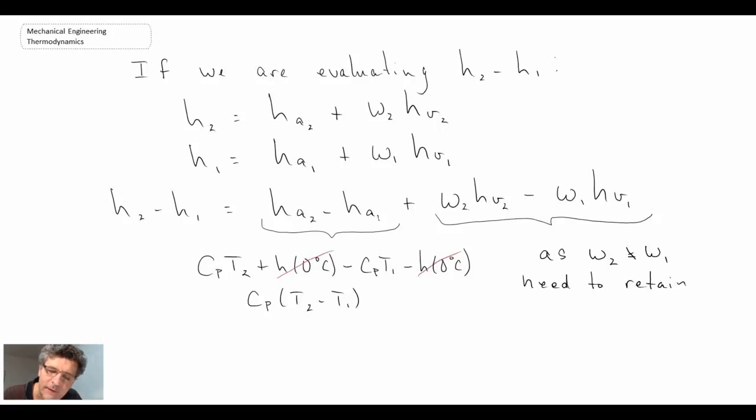We need to retain the full term given that the enthalpy at zero degrees C we said was 2501.3 or something of that order. It might vary depending upon the book that you're using. But given that we can't make the cancellation that we had in the first term and cancel out the enthalpy there because the specific humidity value between two and one will change. But anyways, that gives us an approximation for calculating enthalpy change per kilogram mass of dry air.